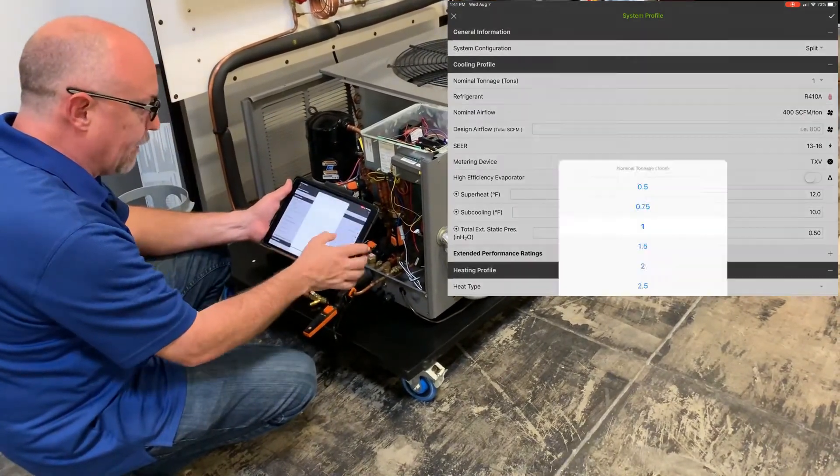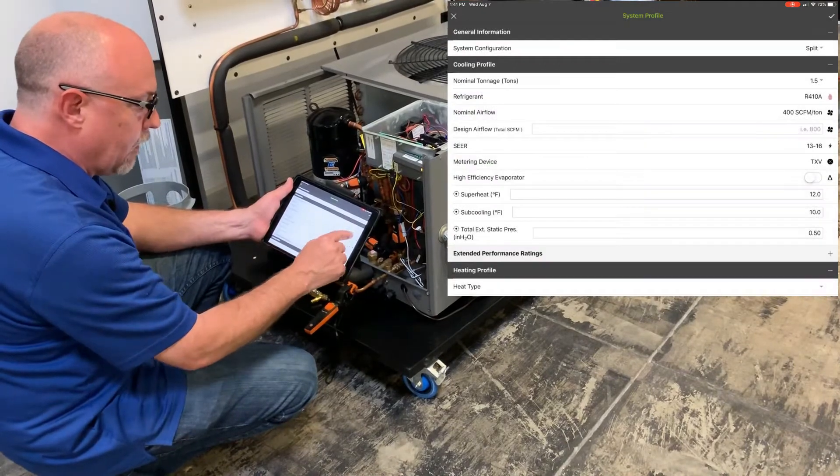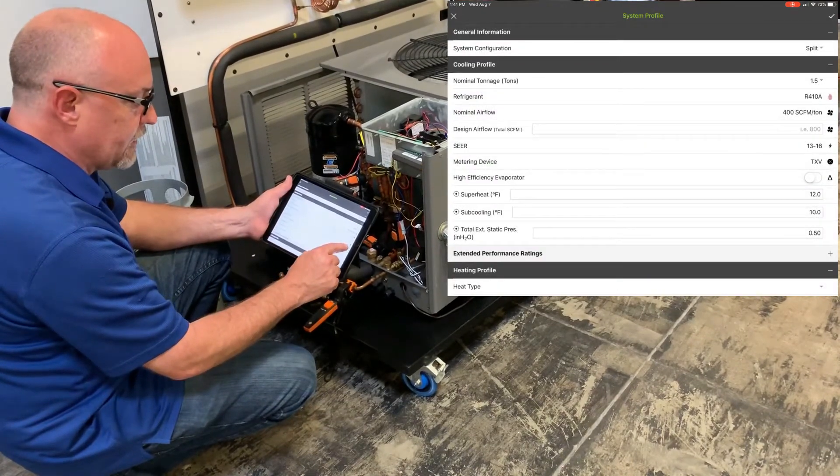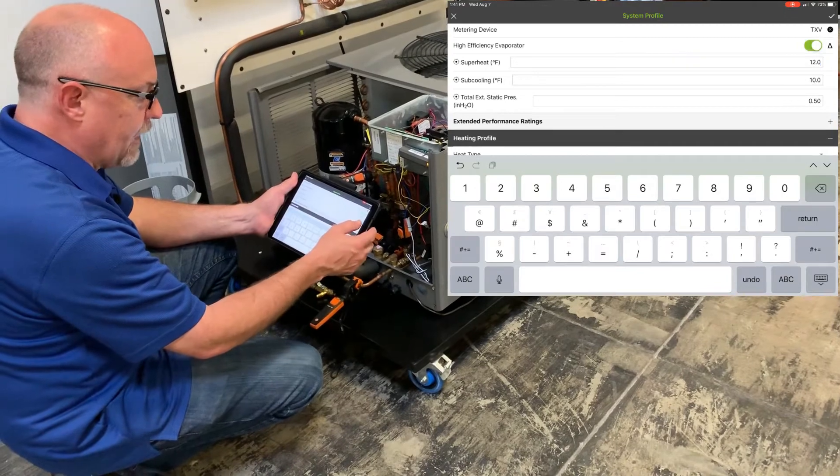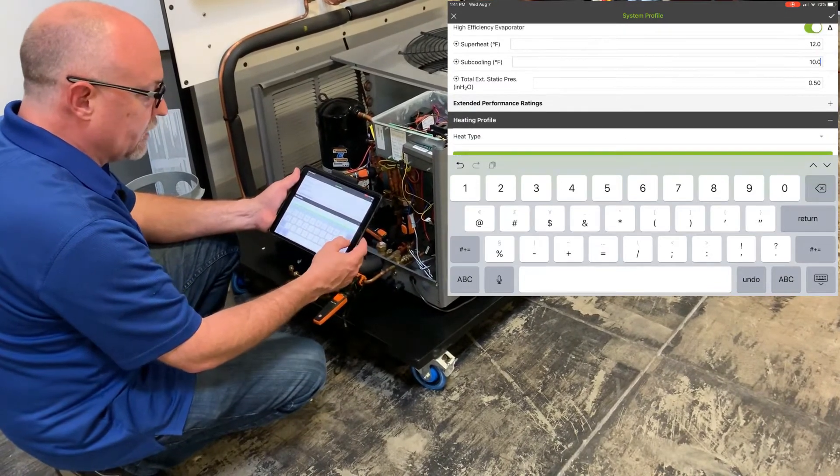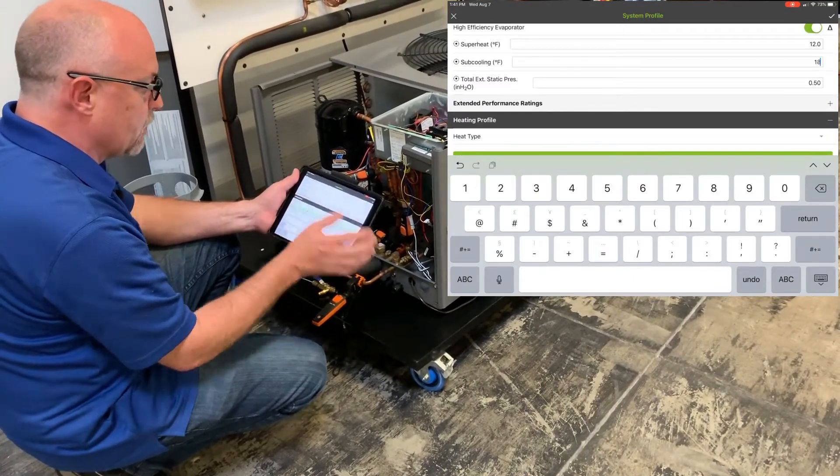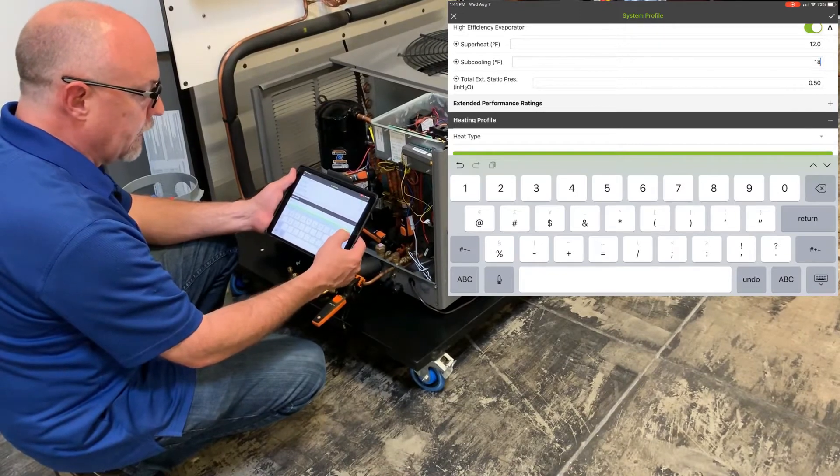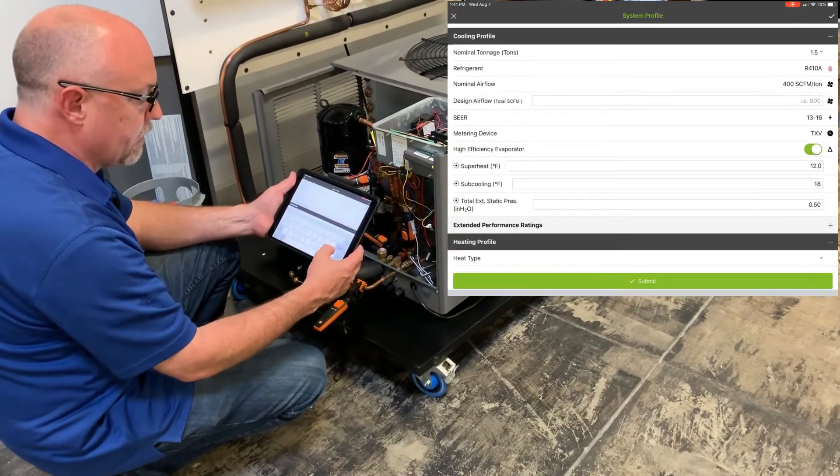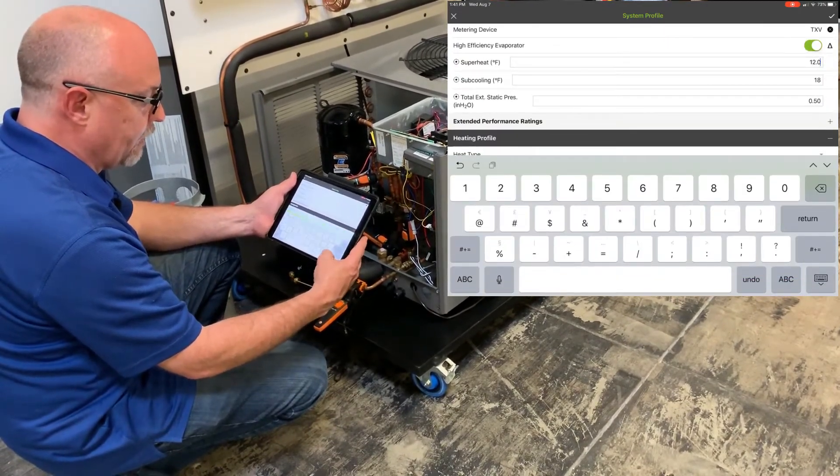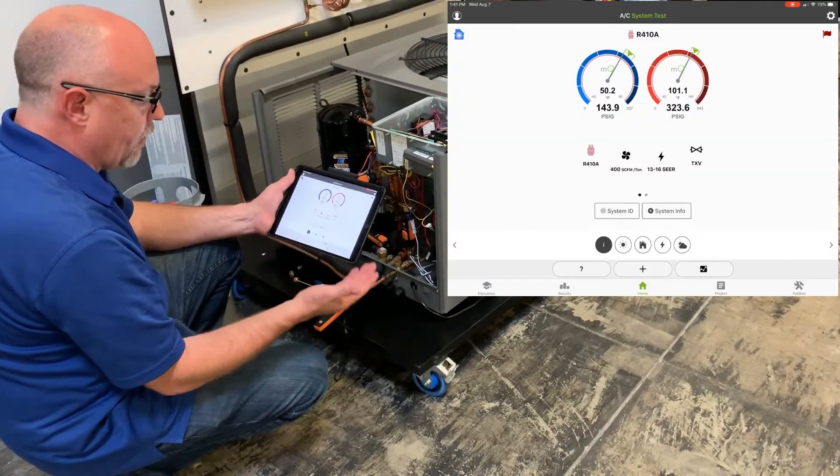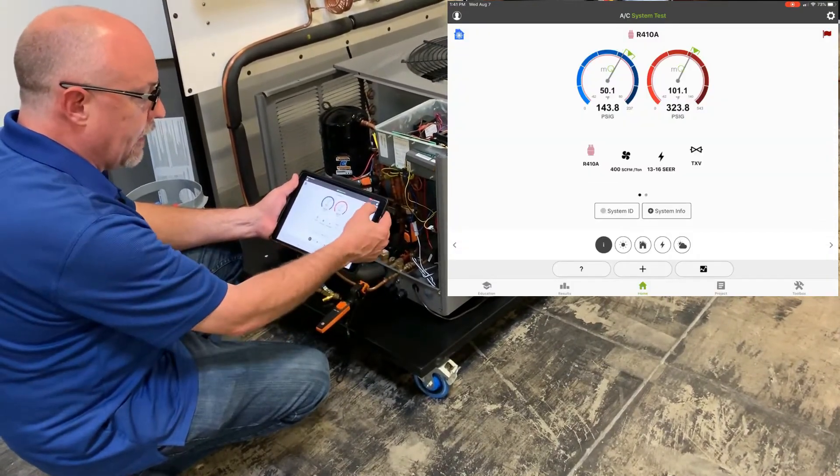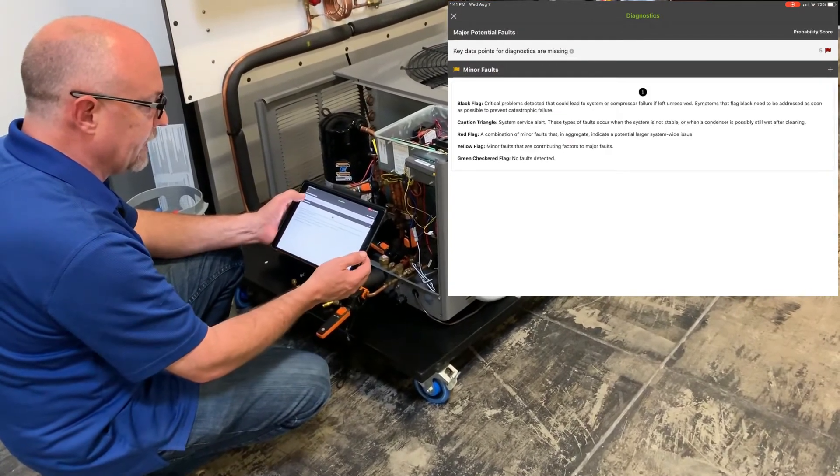And this is a ton and a half system. We'll set it up a ton and a half R410A, 13 to 16 SEER. It's got a TXV. It is a high-efficiency evaporator coil. My sub-cooling target is 18 degrees, which I get from my manufacturer's label. And then all I need to do now is hit the down key for the keyboard and hit Submit. And then I have all my targets set up for MeasureQuick and it allows me to quickly access my diagnostics.